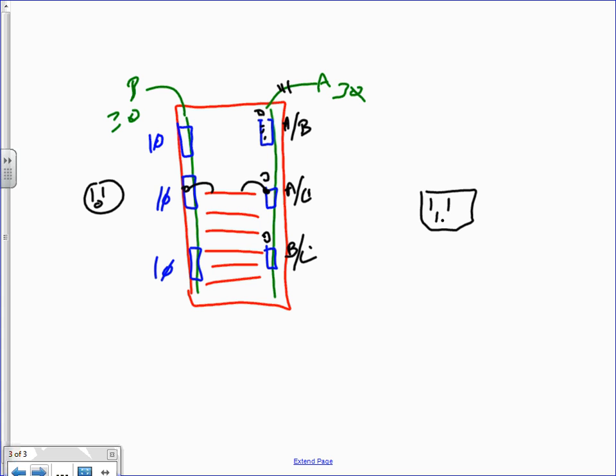But it's a challenge because you go up and down these rows and rows of computer equipment in these data centers, and some folks just start the rack from the bottom and put in filler panels, because our mechanical guys say you've got to blank it off to control air. And well, guess what, they're plugging everything into one side. Then you wonder why you have such a huge phase imbalance back at the PDUs and UPSs. You end up with a grossly imbalanced load.